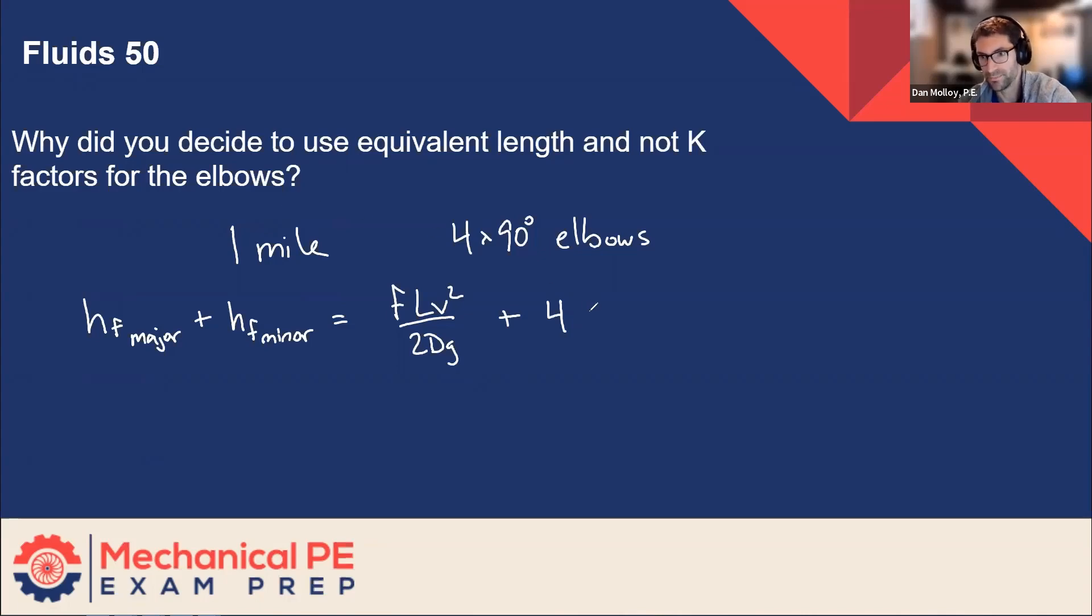And since there's four elbows it'd be four times K v squared over 2g. And then you'd be looking up these K factors in some table for a 90 degree elbow.